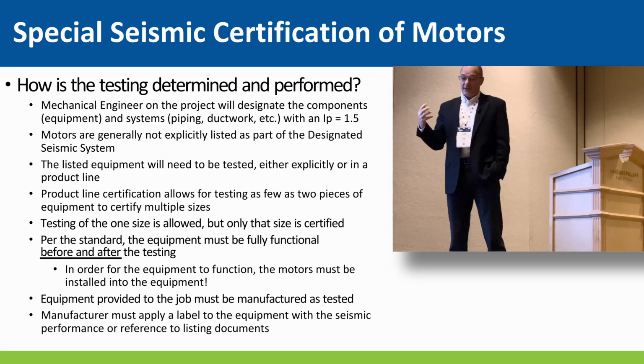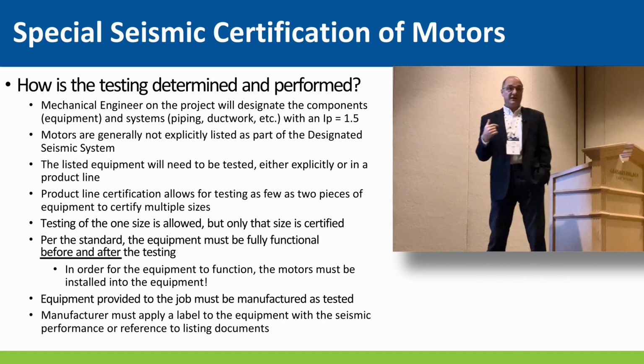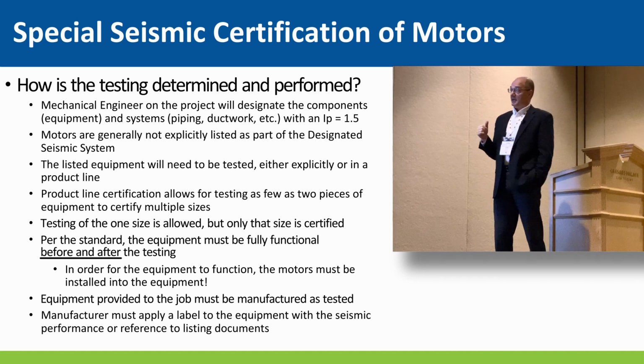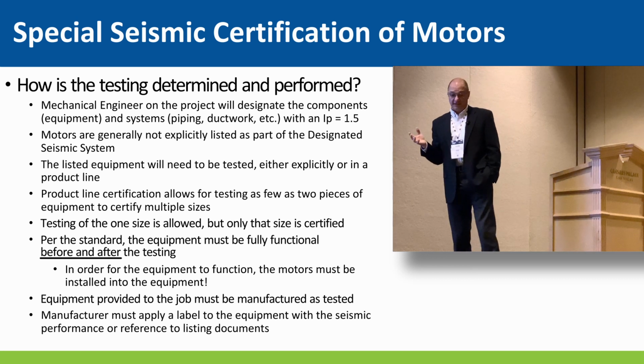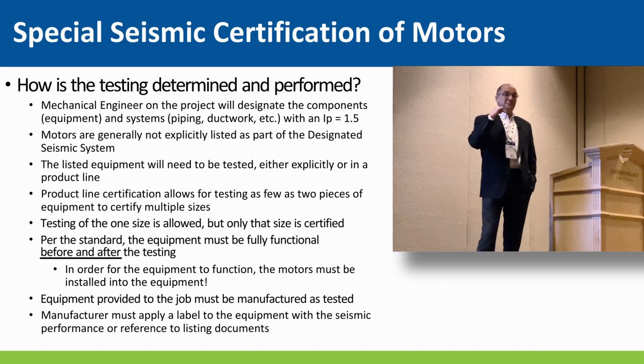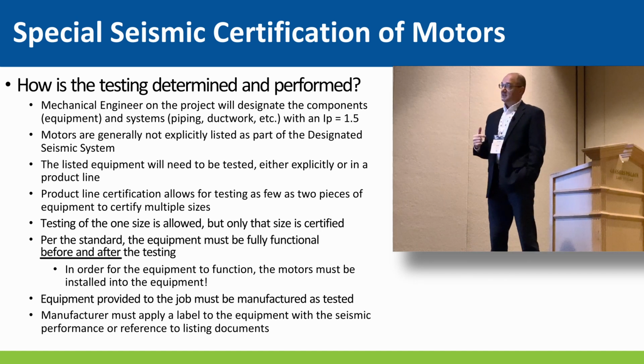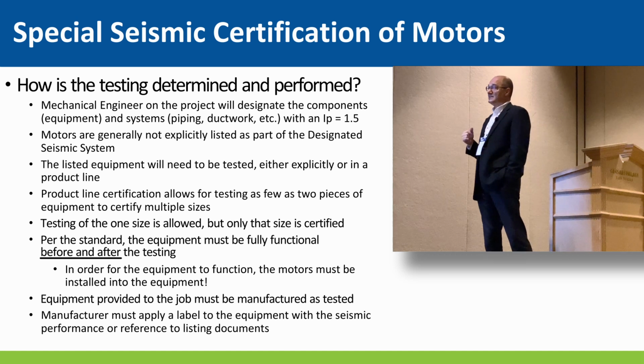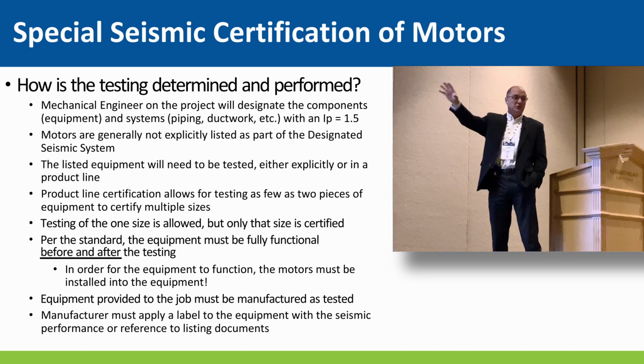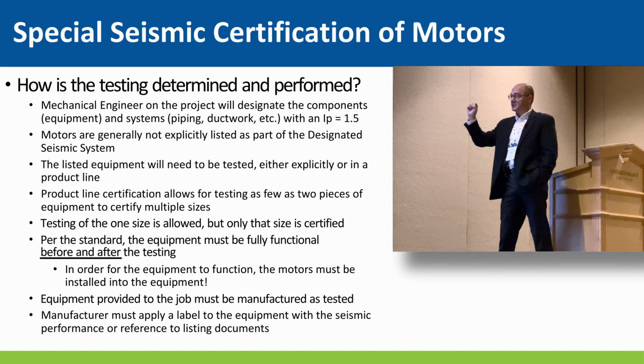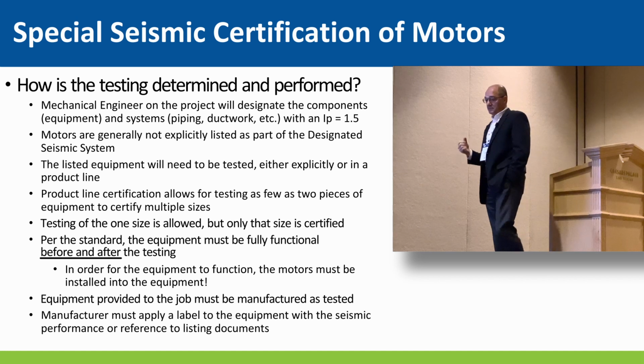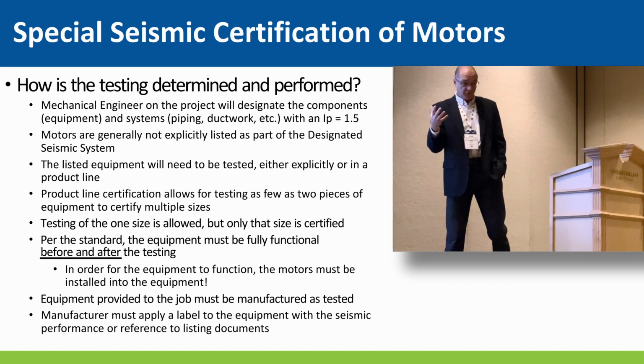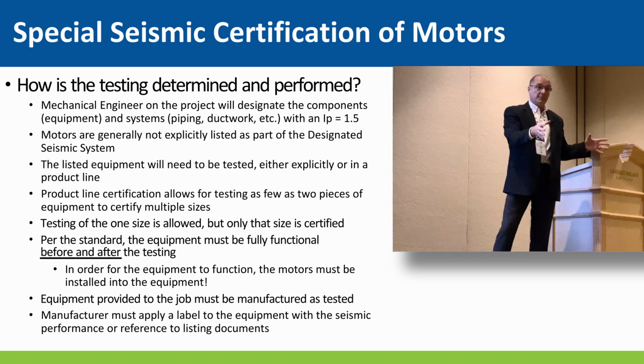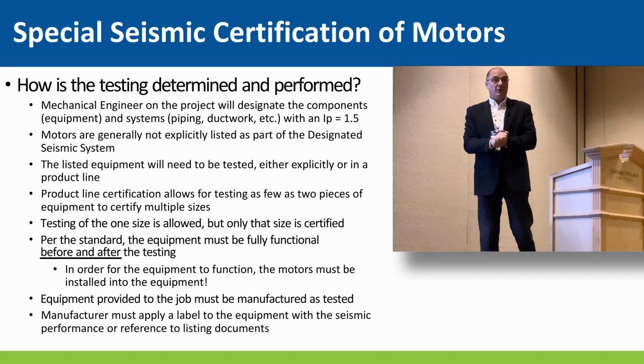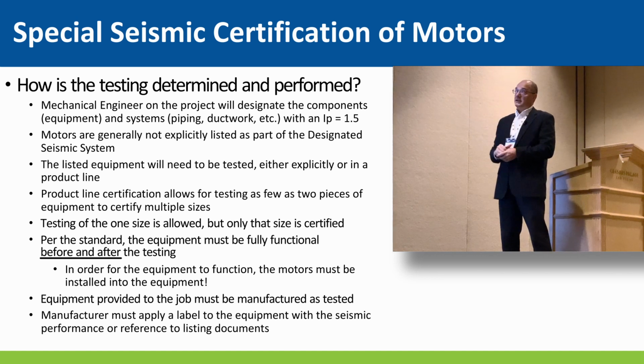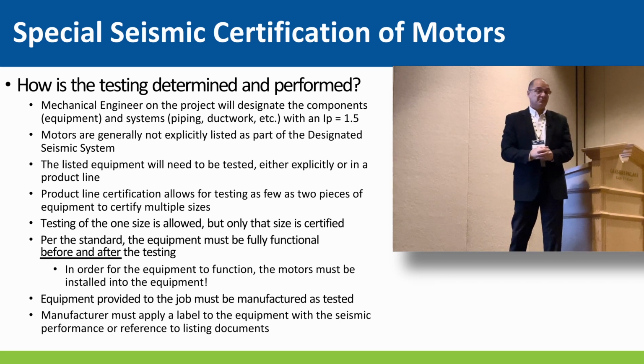All right, so now the engineer on the job will go through that component importance factor and assign the Ip to all the equipment. And the motors are not generally listed as part of the designated seismic system. The equipment that your motor is put into is listed as part of the designated seismic system. And the listed equipment is what needs to be tested through a product line, or those few exemptions that are there with the or, even though it says explicitly. And now the equipment manufacturer is going to decide, well, do I just want to certify my one box? But I make 10 size boxes. So I want a product line certification. So they can go through that ahead of time, before that job comes up, and get their product line certified.